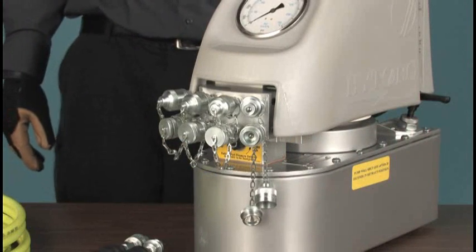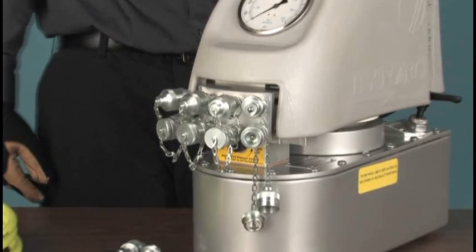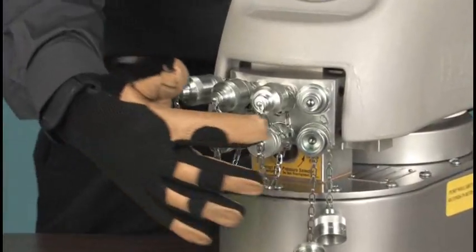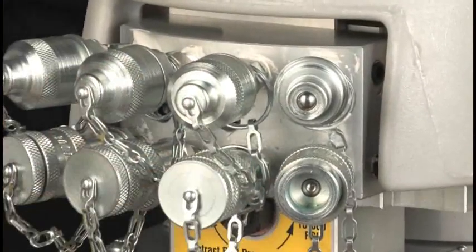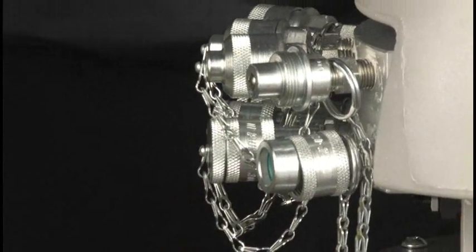Standard pumps come with four sets of male-female couplers which allow up to four wrenches to be connected at the same time. The couplers feature check ball fittings which must be completely engaged for oil to flow. This is an important safety feature of these high pressure units.